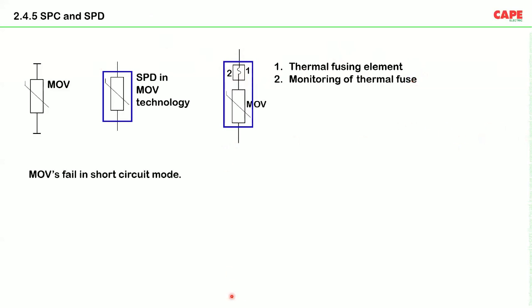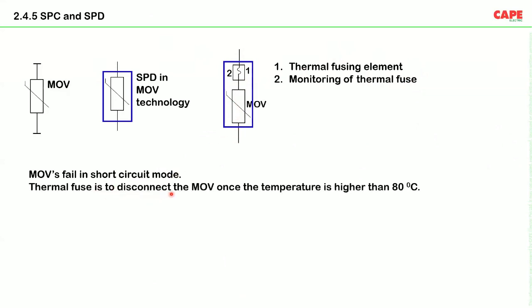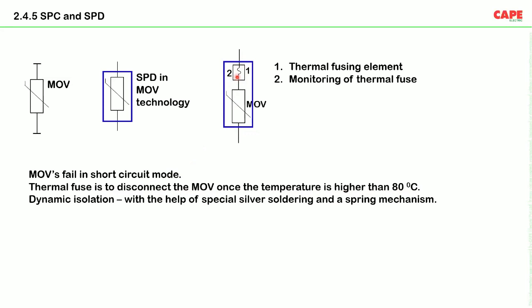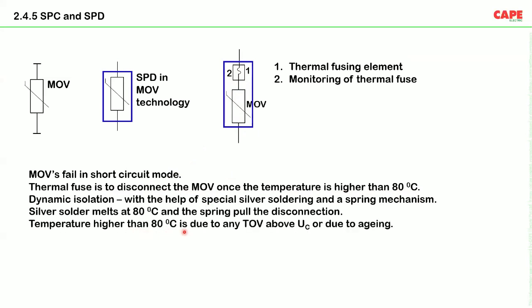What is a thermal fuse? MOVs always fail in short circuit mode. In the sense, at the end of life of this device, it creates a short circuit. Now, the thermal fuse is to disconnect the MOV once the temperature is higher than 80 degrees centigrade. There is a thermal fuse, which is actually a silver soldering and a spring mechanism. Almost all manufacturers follow the same system. Once the temperature of this combination is more than 80 degrees, the silver soldering element melts and the spring removes the MOV from the circuit. The temperature higher than 80 degrees is due to any temporary overvoltage above UC or due to aging.